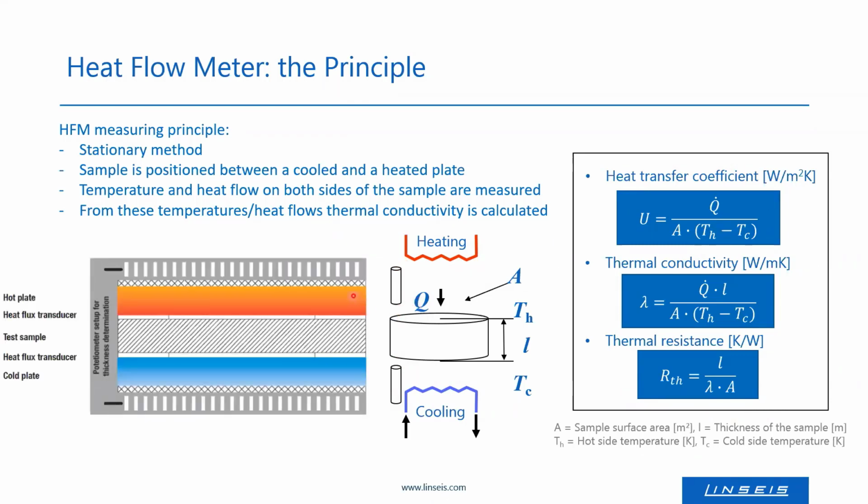In an instrument, this is presented like this. In a schematic drawing, you will find the heated plate on top, a heat flux transducer, the sample, the second heat flux transducer, and the cooled plate.